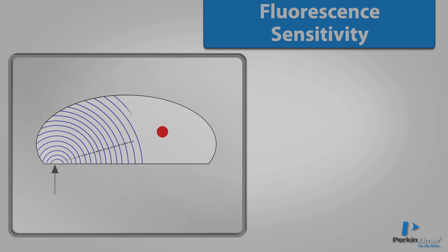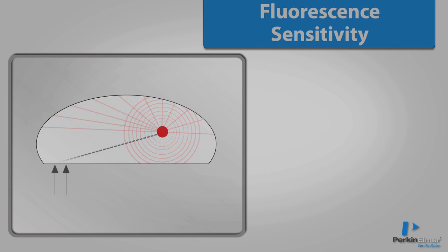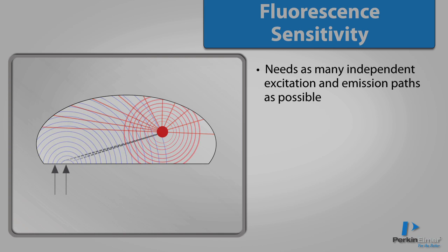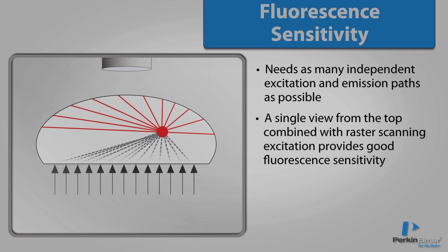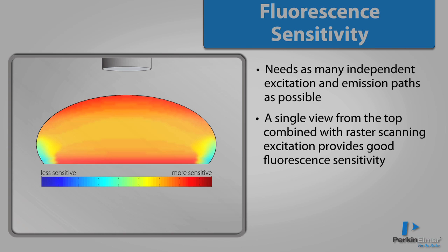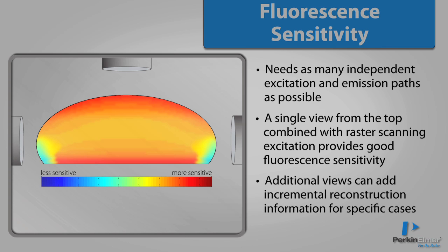For good 3D reconstructions, the instrument needs as many independent excitation and emission paths as possible. A single view from the top combined with raster scanning excitation provides good fluorescent sensitivity for most cases. Additional views can add incremental reconstruction information for specific cases, for example along the sides of the animal, but will limit instrument throughput and flexibility.